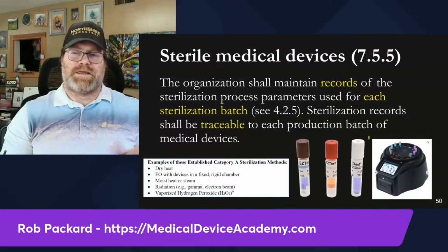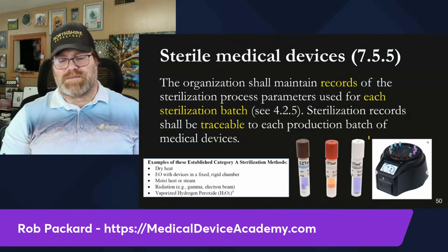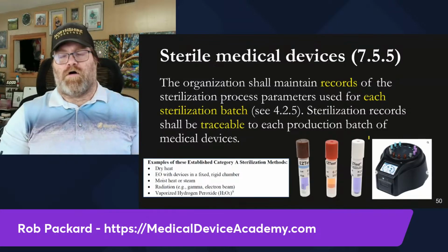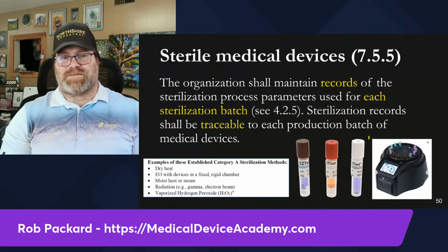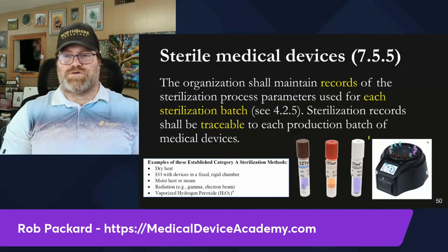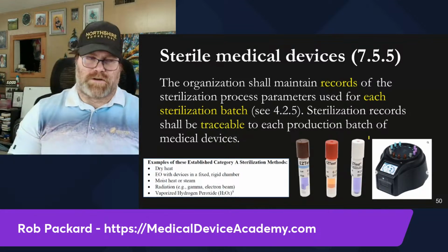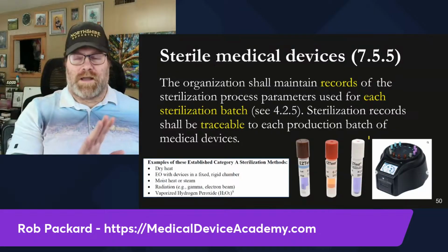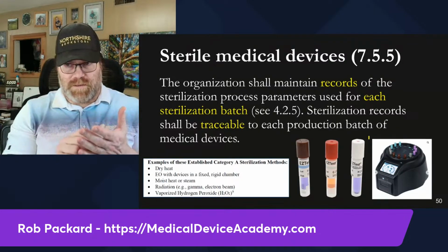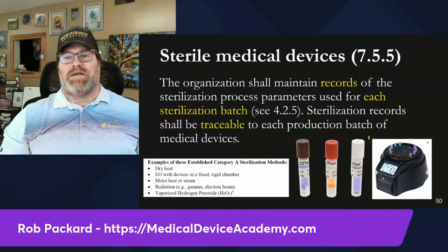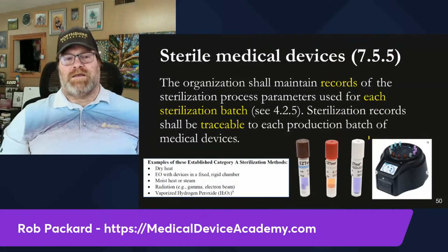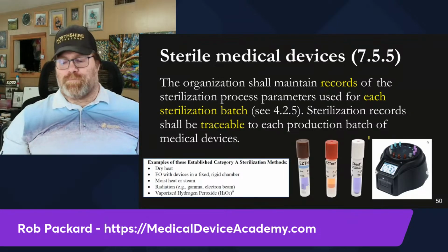Self-contained BIs eliminate the need for a microbiologist to do the testing. Very easy to use, foolproof, validated, automated, and tracks everything and gives you a report that you can include in your DHR or batch record. So that's really where we're at now. We're not in the Stone Ages where we're filling in forms and asking microbiologists to make sure it was filled in right. You can validate all that and then just follow the procedure and do your monitoring and keep records of it.